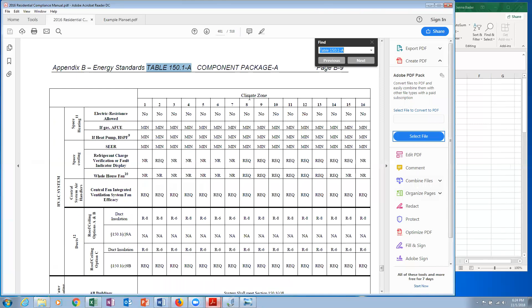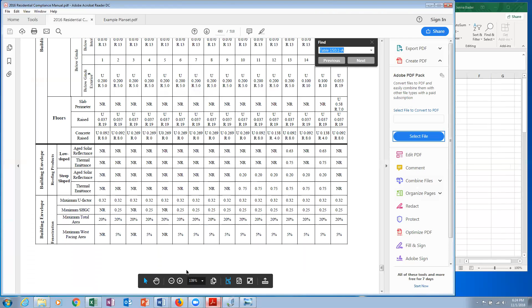I'm going to go back to that prescriptive package A document in the building plans to find these minimum values. Climate zone 2 is in the second column. The window maximum U factor is 0.32. We could go lower than that if we wanted. I think an acceptable range would be like 0.18 to 0.32.